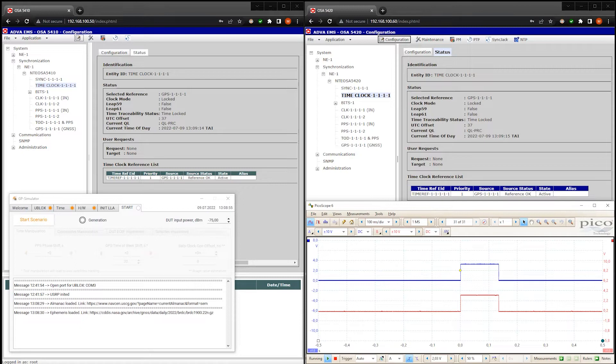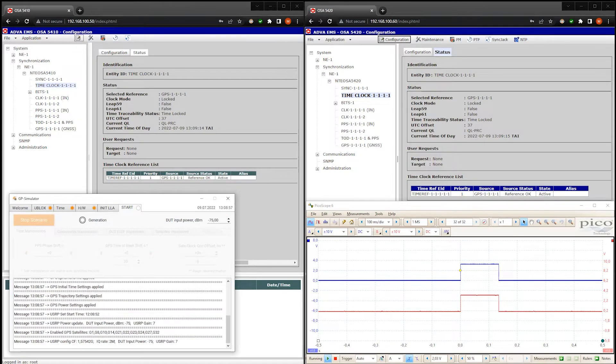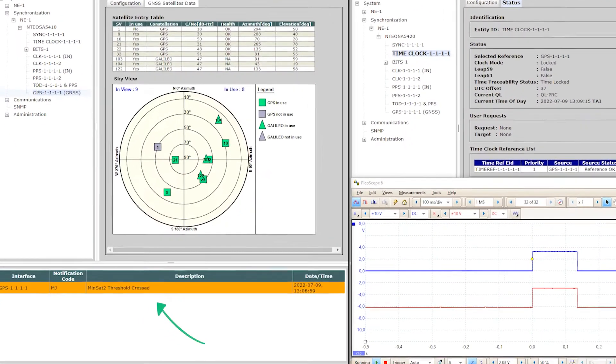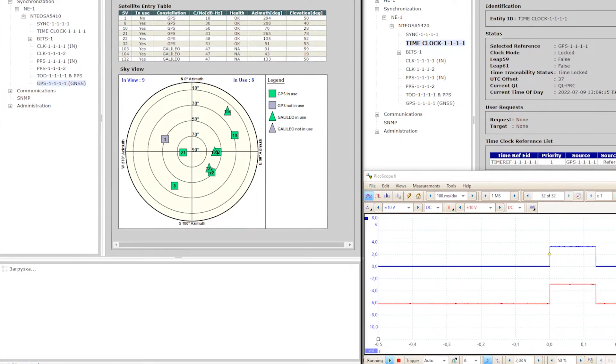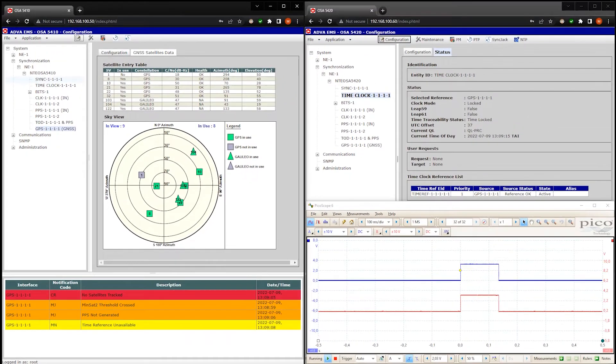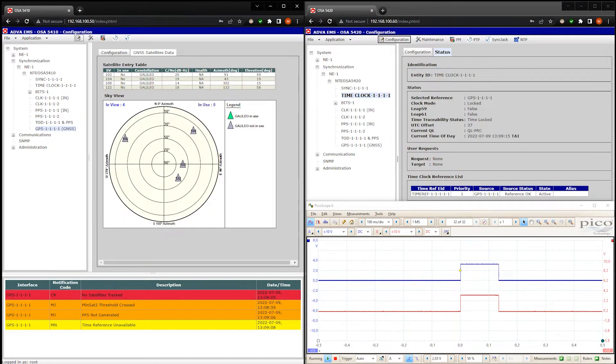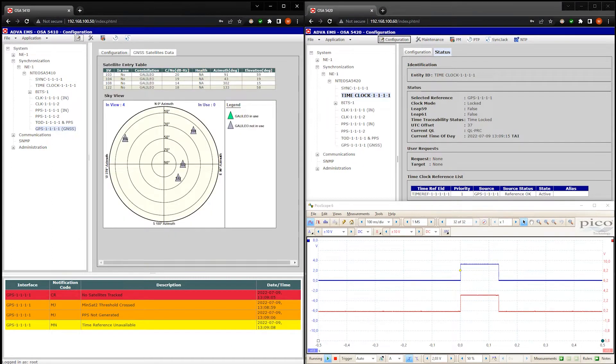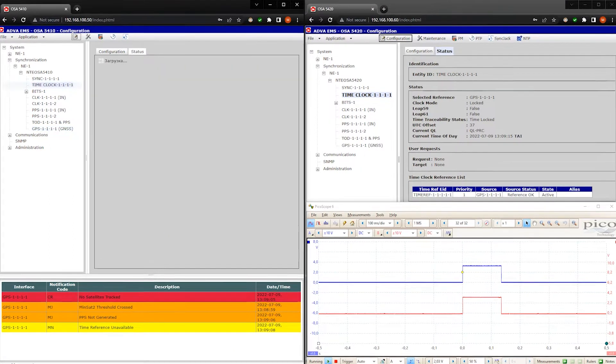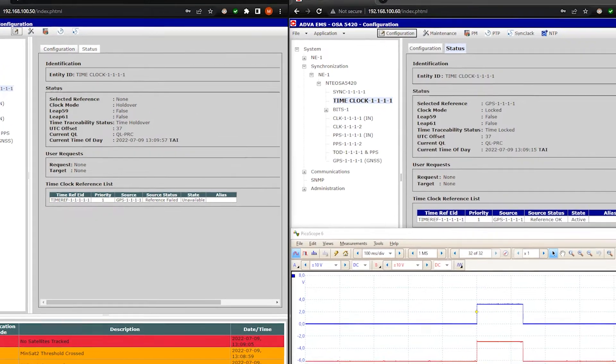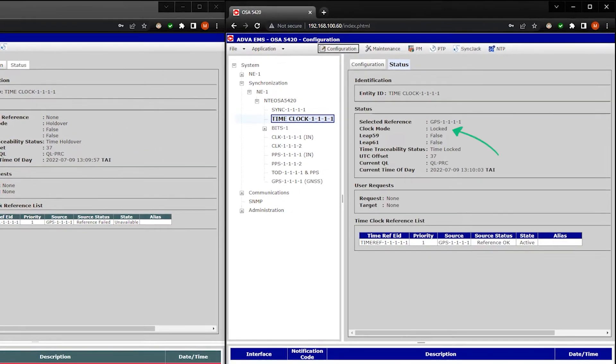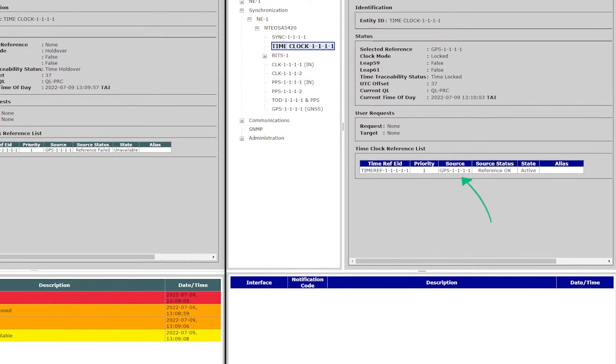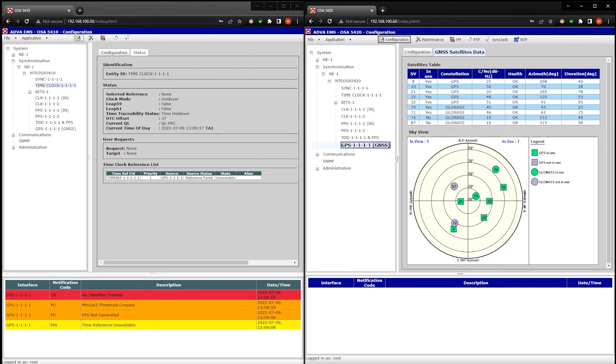At the bottom you see the warning and error messages that the GNSS satellites are not visible. This is a normal scenario for a non-coherent spoofing attack. GPS satellites disappeared. Let's now check the clock status. Time server has gone into holdover mode. Let's take a look at the reference time server. It's locked. The GPS module is active and all satellites are clearly visible.